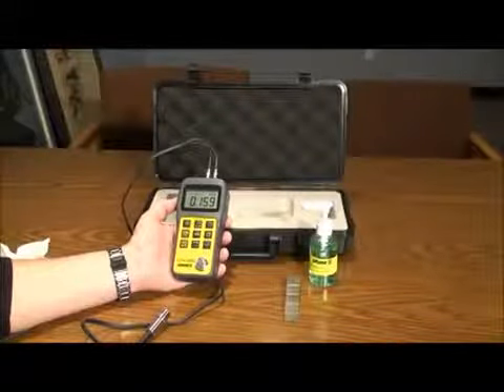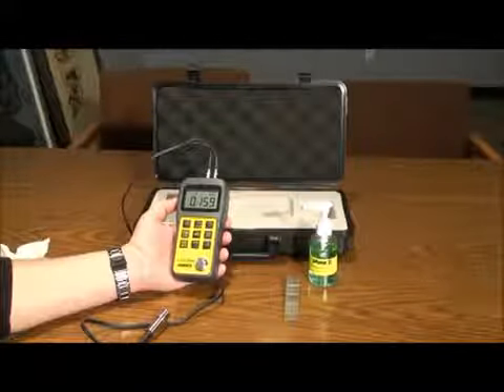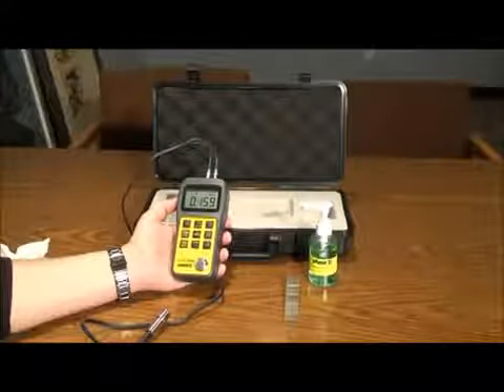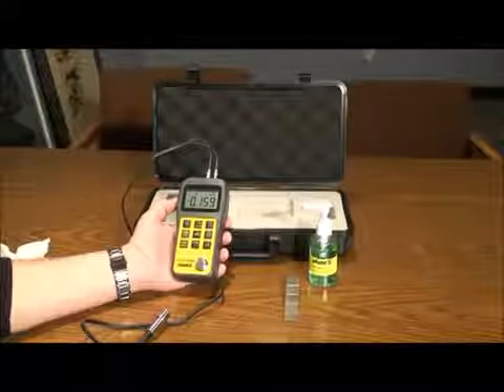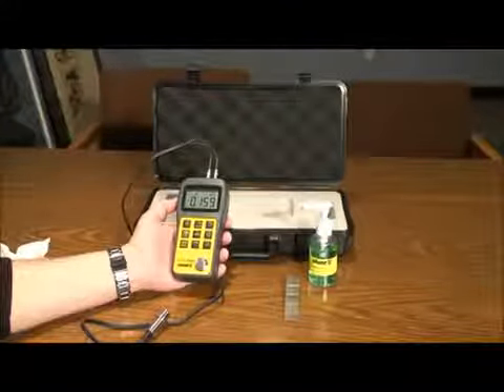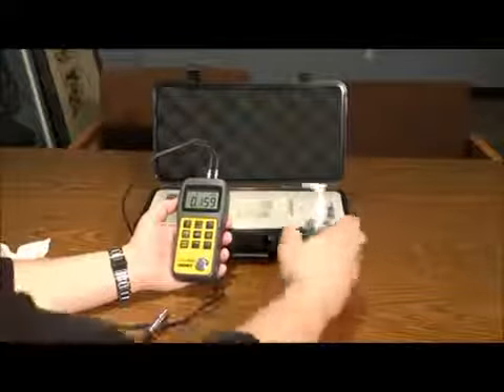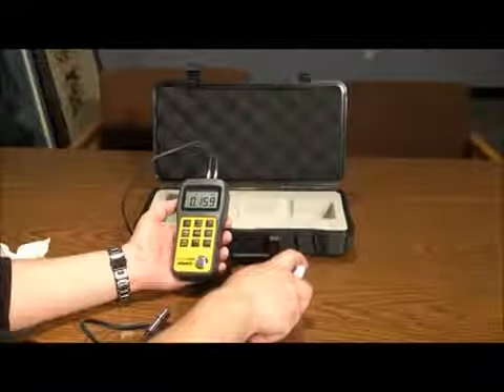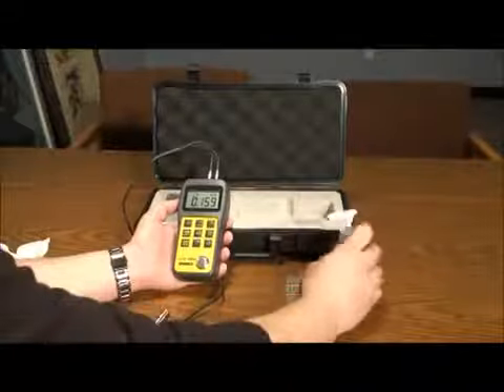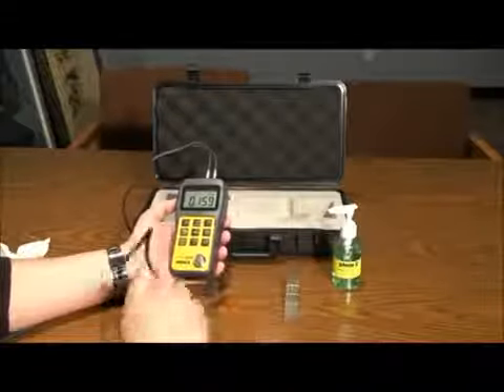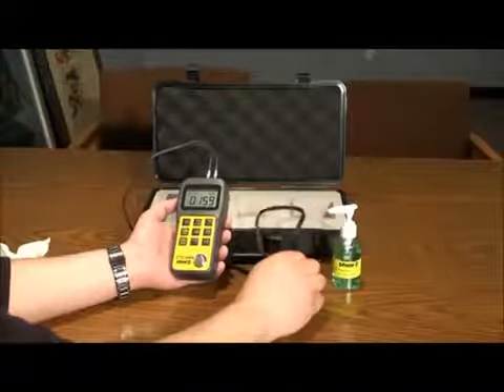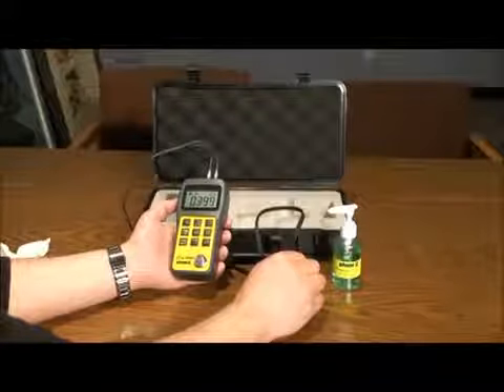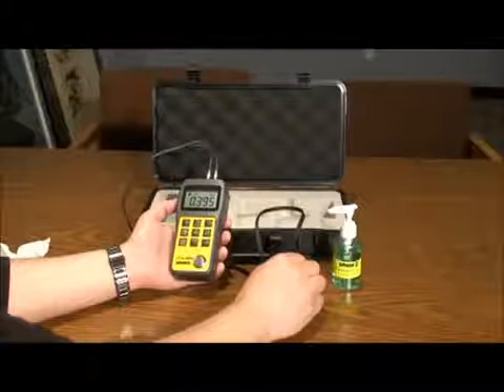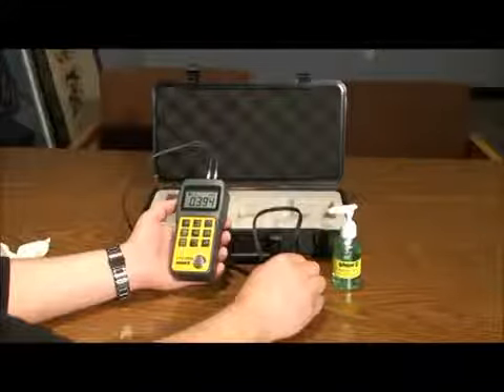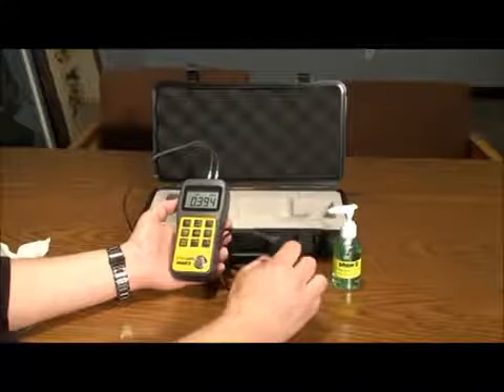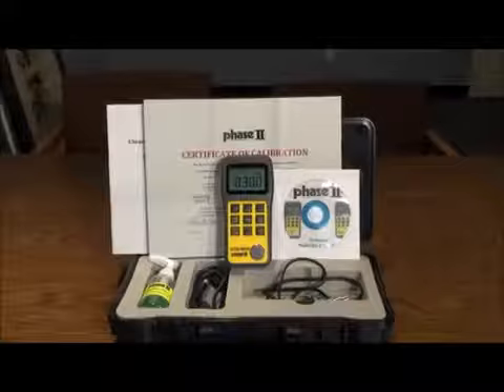Taking tests is very easy. After making sure your measuring parameters are set correctly, inch or metric and velocity of material, place a small amount of gel on the workpiece and then follow with the probe on the workpiece. Readings will show on the screen. Be certain not to use too much gel. Use just enough to remove air from between the probe and the test material.